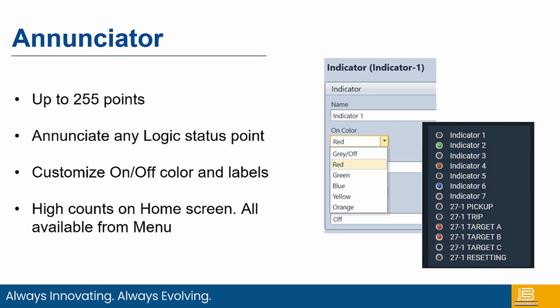The annunciator is on the lower right quarter of the protective relay and on the home screen, and you can have up to 255 points in our indicators. On the home screen, depending upon the length of the name, we can show up to about 12 or 14 of them. 7 or 8 is typical if you're using potentially 2 lines each, but you can do more if you wish, and you can color code them, and annunciate any logical point in the relay.